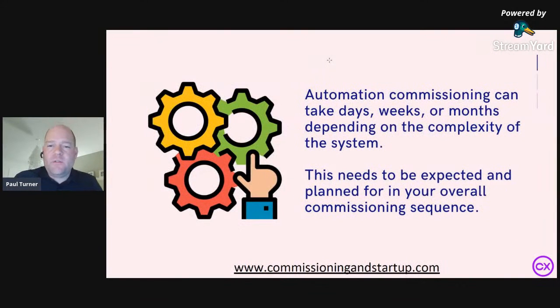You're going to want to go through all of those scenarios to test each of the fault conditions. This automation commissioning, depending on the complexity of your system, can take days, weeks, or months. On the last project I worked on, a $5.2 billion HVDC project, we went through automation commissioning for close to a year to test all the stability controls, all the normal operating conditions, all the fault conditions, and all the electrical equipment to confirm everything was functioning as an HVDC system.